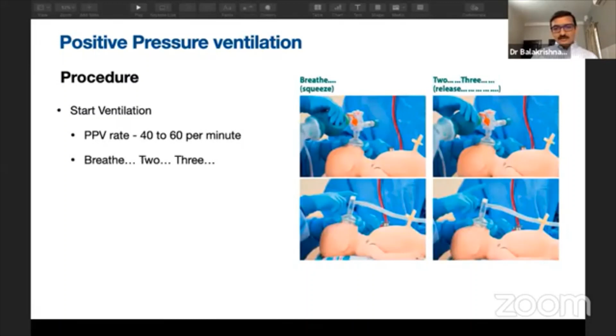Once we have achieved a good seal, we have to start ventilation. The ventilation rate is 40 to 60 per minute in the sequence of breathe, 2, 3, wherein during breathe we squeeze and during 2, 3 we release. And the peak inflation pressure that can be delivered when we are using a T-piece resuscitator is around 20.